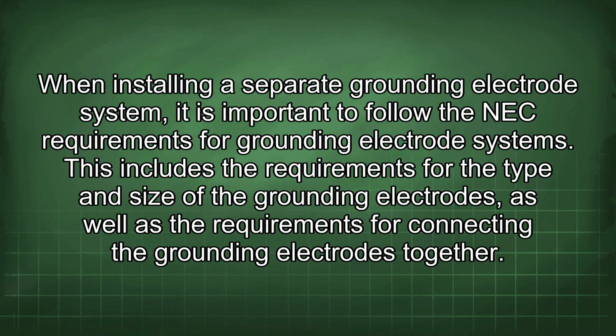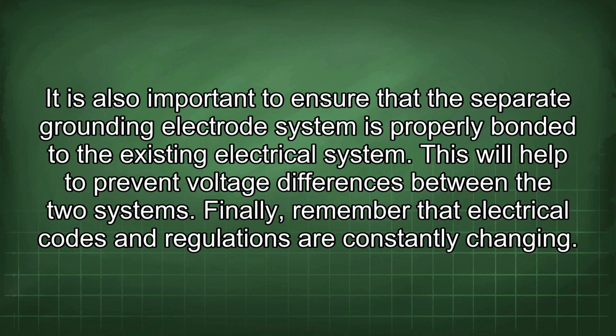When installing a separate grounding electrode system, it is important to follow the NEC requirements for grounding electrode systems. This includes the requirements for the type and size of the grounding electrodes, as well as the requirements for connecting the grounding electrodes together. It is also important to ensure that the separate grounding electrode system is properly bonded to the existing electrical system. This will help to prevent voltage differences between the two systems.